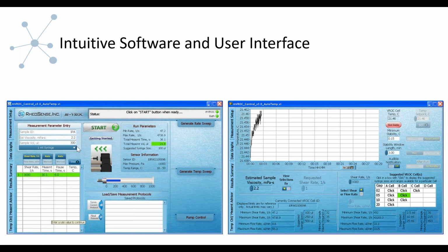Once this is all inputted, then the run parameters section will be populated. And this gives you an idea of what your minimum shear rate and maximum shear rates are. With our technology, because it is pressure driven, the optimal operational range is 5% to 95% of the maximum pressure that the chip can handle.